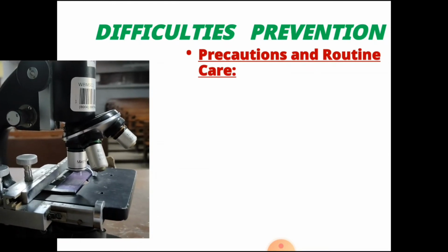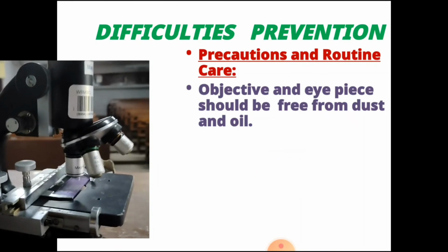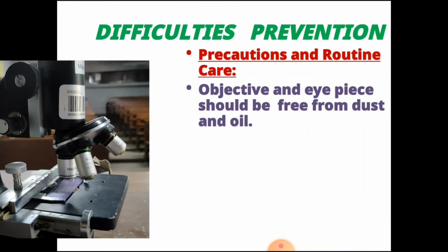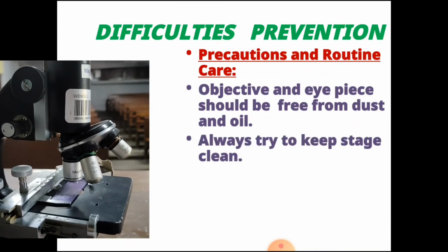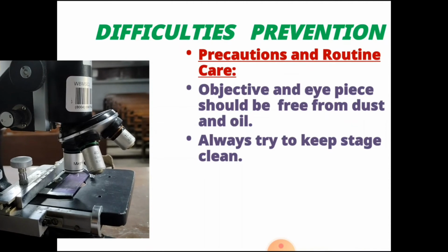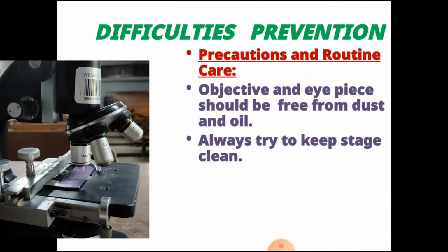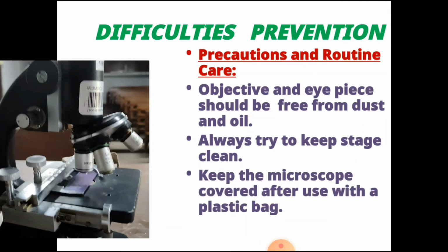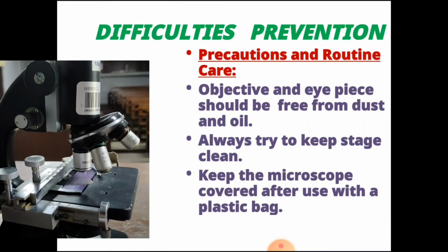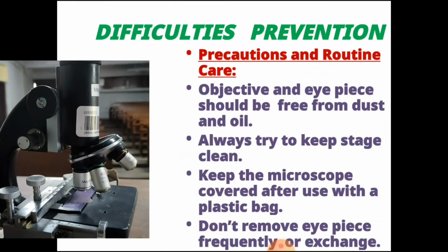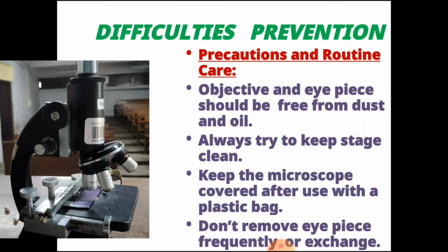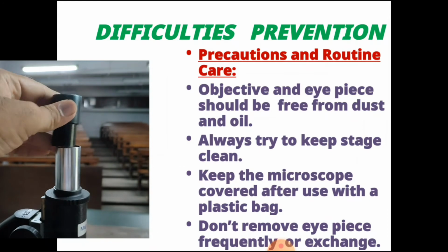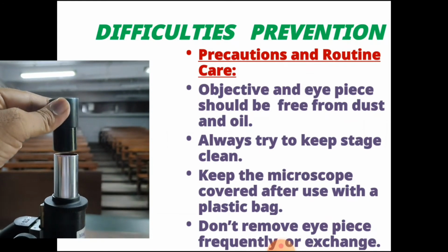Now, the precautions and routine care. Objective and eyepiece should be free from dust and oil. Always try to keep the fixed stage and mechanical stage clean. Keep the microscope covered after use with a plastic bag. Don't remove the eyepiece frequently, or exchange the eyepiece with another microscope.